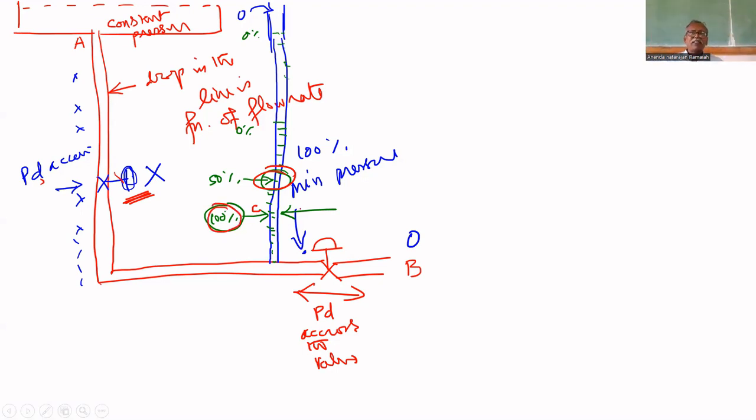I can do the experiment. That experiment is called inherent characteristics. What you have to do for 100% flow rate is check the column level in the single column manometer. A single column manometer means a transparent tube connected just before the valve. The level in that single column will be minimum for 100% and maximum for 0%.